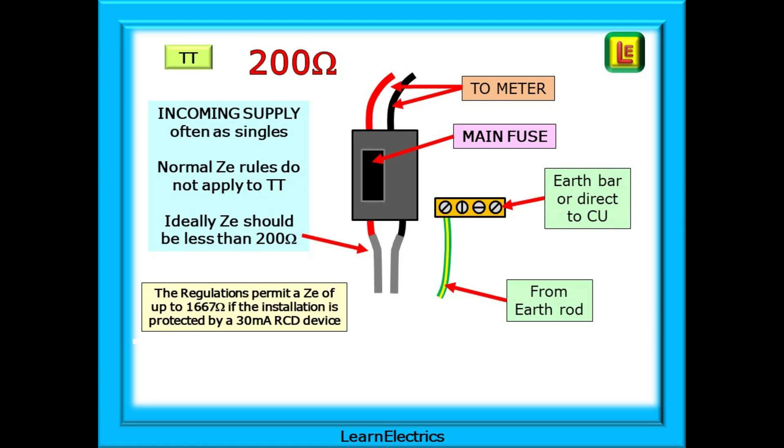Do not confuse TT systems with TNS types. A TT system has no earth going to or coming from the cutout box. Learn to recognise this system. There is a phase conductor to and from the cutout and a neutral conductor to and from the cutout and that is it. The earth conductor is separate and comes from the earth rod. It may go to an earth bar or it may go directly into the consumer unit.